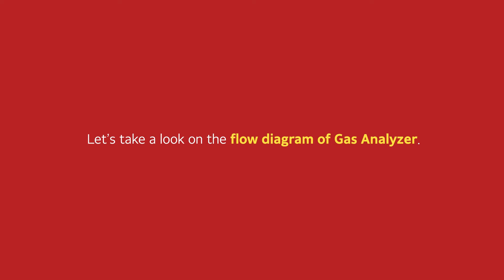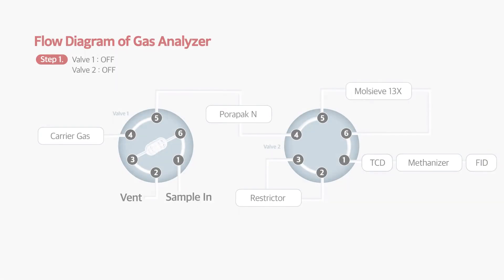Let's take a look at the flow diagram of the gas analyzer. When all valves are off, the sample is loaded in the loop. Turning on valve one, the sample flow is switched for injection. Hydrogen and oxygen are eluted earlier in Porapak N column and separated in molecular sieve column and then detected by TCD. Carbon monoxide is converted to methane in the methanizer and detected by FID.